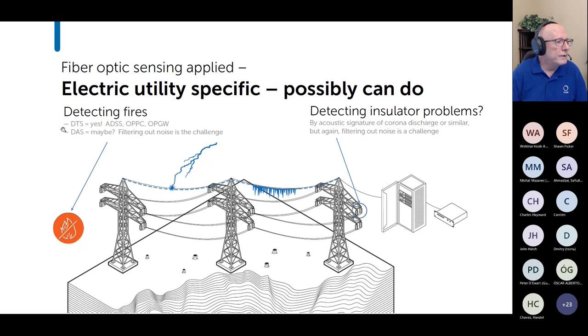I talked about detecting fires. Obviously, if there's a fire under the structure, the cables will heat up, and ADSS would heat up quite quickly. But like I said before, you can do fire rated designs so that you have a certain amount of time before there's going to be a mechanical failure of the cable. You could use DAS technology to sense fire in the vicinity, because when forest fires are burning, they make sounds that are unique and specific. But there would have to be work on setting up the filtering of everyday noise so that you're only detecting the sound of the fire. Likewise, insulator problems have their own unique acoustic signature. The challenge is to filter out the other noises so that you're able to detect what is actually a corona discharge or tracking on an insulator that's going to be failing soon.